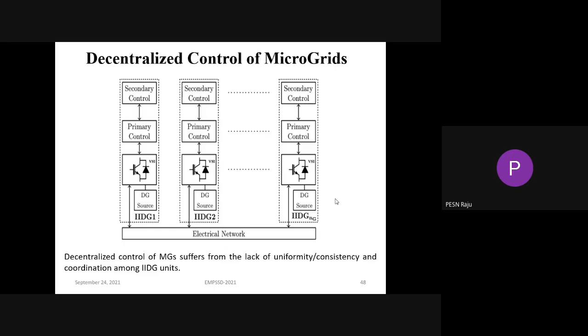This secondary level control loop will communicate with all the primary level control loops, and it will provide the voltage and frequency deviation signals that they have to modify. That will be given through the communication infrastructure. As you can see, we have only one secondary level control loop, all the primary level control loops, and in between, the communication infrastructure. If there is any failure of this communication infrastructure, there won't be any communication between the secondary level control loop and the primary level control loop. So that is the main drawback of this control, a single point of failure.